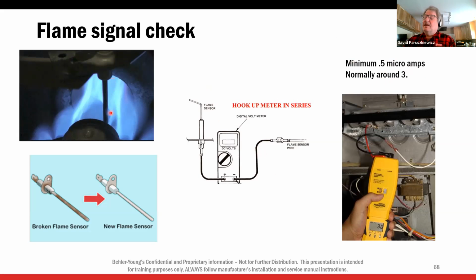Now, again, rust across this will lock this out. Okay, it has to be a flame. That's why it's called flame rectification. Rectify means convert from AC to DC. So we're only taking half the sine wave and passing it through the flame. So when we send the power from the flame rod to ground, the whole thing passes. But as power reverses and goes from the ground to the flame rod, it doesn't catch most of it. So we basically catch half the sine wave, or a DC voltage. So if you put a screwdriver from here to ground, it'll lock it out because it knows it's a short. Okay.